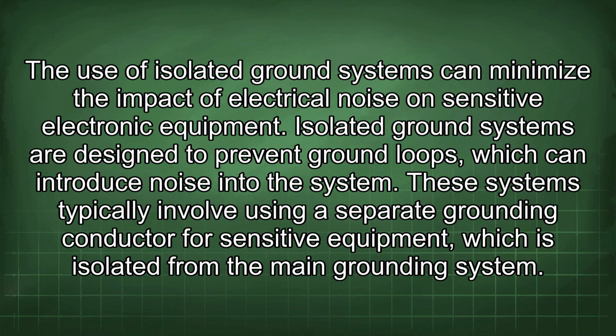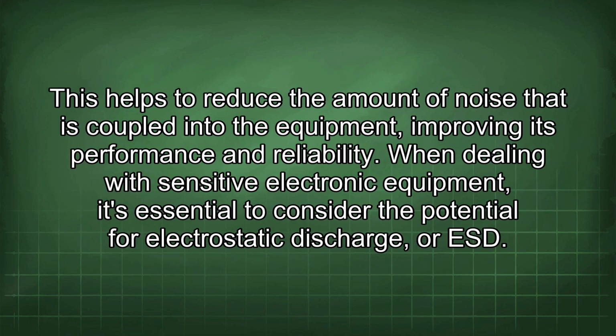The use of isolated ground systems can minimize the impact of electrical noise on sensitive electronic equipment. Isolated ground systems are designed to prevent ground loops, which can introduce noise into the system. These systems typically involve using a separate grounding conductor for sensitive equipment, which is isolated from the main grounding system. This helps to reduce the amount of noise that is coupled into the equipment, improving its performance and reliability.